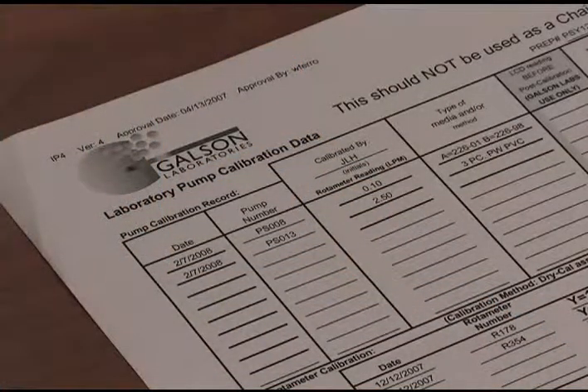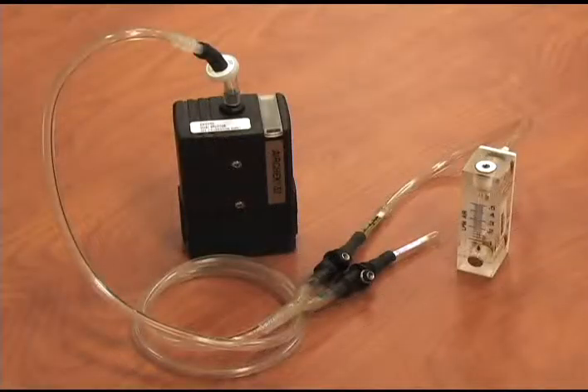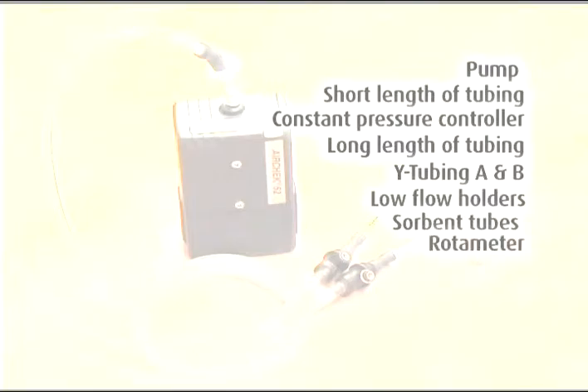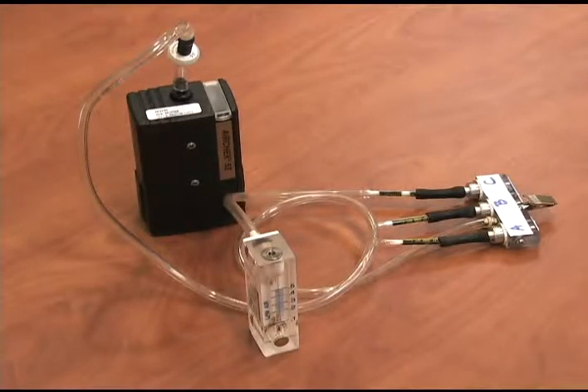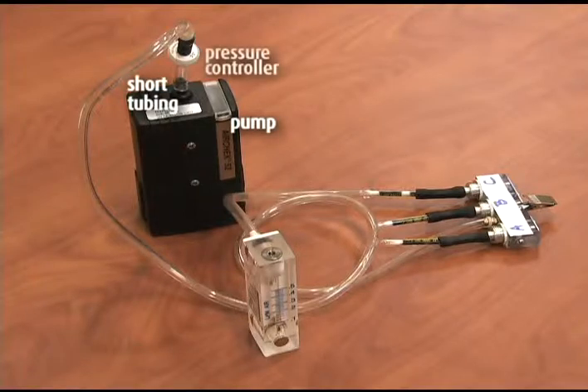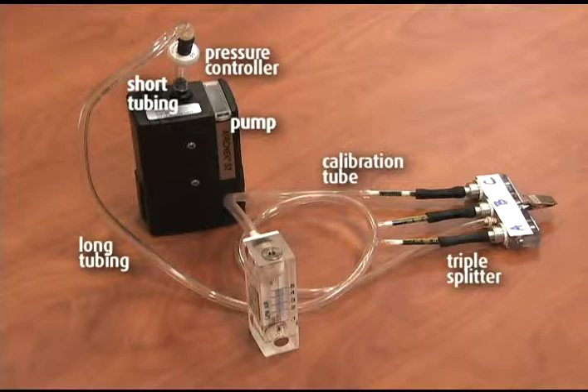All pumps have the lab calibration information on the pump calibration data sheets provided. Set up the pumps with the correct media in line, with the field rotometer as shown. The order of the components for dual splitter calibration is pump, short length of tubing, constant pressure controller, long length of tubing, Y-tubing marked A and B, 2 adjustable low-flow holders, sorbent tubes, and rotometer. For calibration of triple splitters, set up the calibration sampling train as follows: pump, short piece of tubing, constant pressure controller, long tubing, triple splitter, calibration tube, and rotometer.